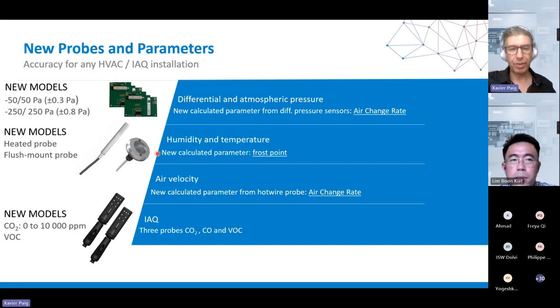It's almost super discreet. It has also a front filter that allows this probe to be used also in VHP environments. So same thing as the CPE and the C320. They are resistant against the VHP, the vaporized hydrogen peroxide. So this is the same thing. This filter allows the probe to be ready to resist this cleaning agent easily. So there's no problem for that. The response time, even though we have a harsh filter, is quick. It's pretty quick. I mean, it's one of the best in the market as well.